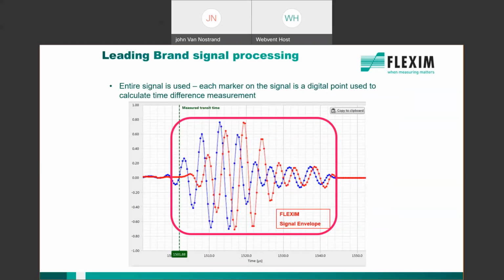So when you first start up the meter, we can look at the signal to correlated noise ratio, and that essentially gives us an indication that we've got a good transmit signal, and it's a great diagnostic tool for setting up the meter to ensure that we have stable measurement.